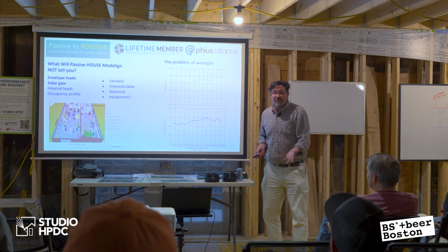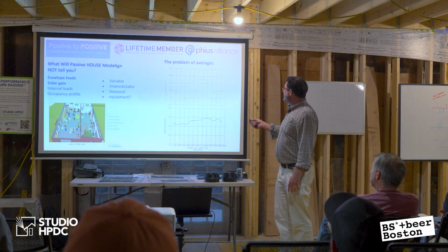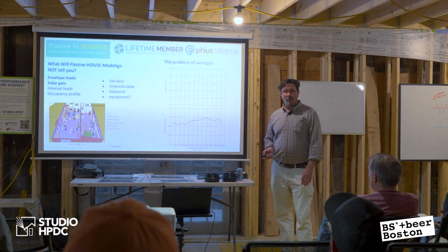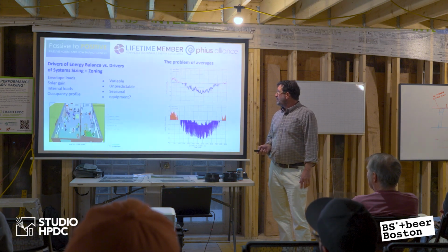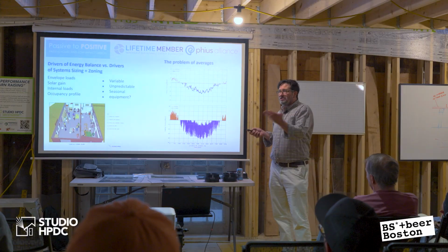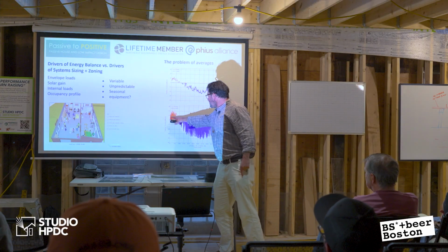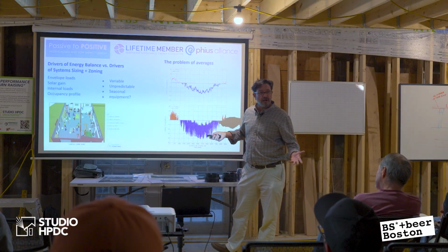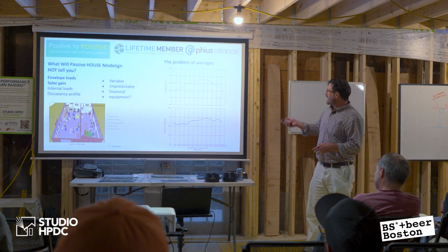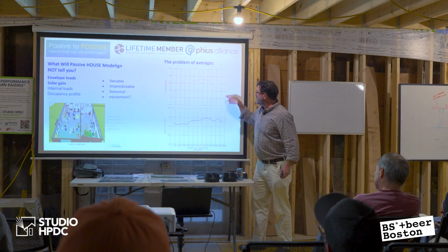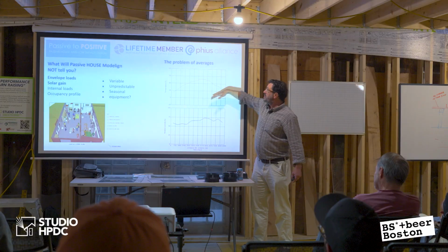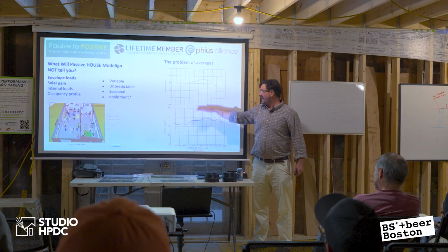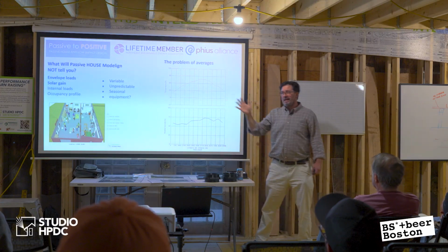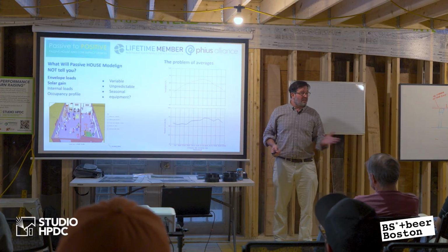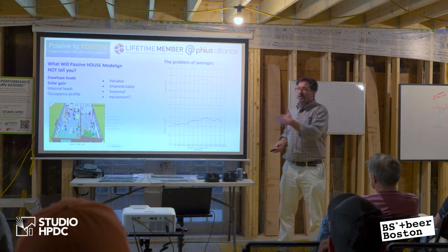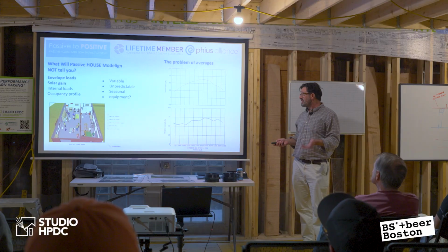Okay, what does passive house tell you and what does it not tell you? It tells you this. Oh, those are our average temperatures. Oh, there's our average relative humidity. Well, what is actually happening? Something way different. The averages are these smooth lines and they miss that between the average here and the peak is double, right? I lost a slide there, but there's supposed to be this slide, which is nice and smooth, and then the hourly is big and the temperature range is much more dramatic. And the humidity, as you were pointing out, is a huge part of loads, which has to be understood. And passive house will not tell you this. Any passive house consultant says, oh, I know how to tell you this. I mean, only if they're an engineer and are doing other calculations can they really say that with confidence.